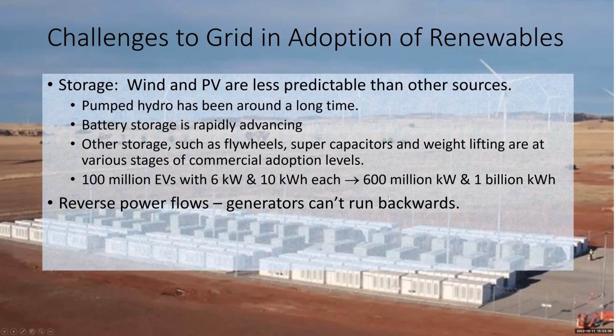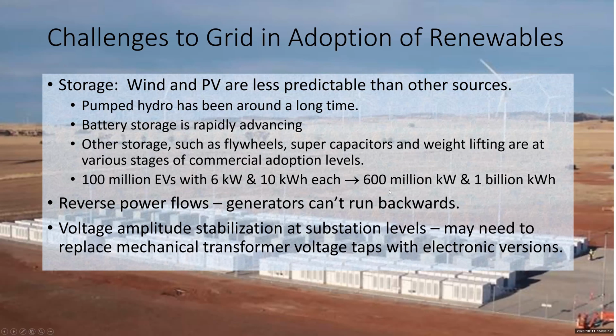But this is a recognized and doable problem - folks already know how to solve it. There's voltage amplitude stabilization at the substation level. What that's saying is that if the amplitude varies, the taps at the substations might be moving up and down more than they otherwise normally would, in order to maintain a relatively acceptable voltage level at the end of the distribution line.